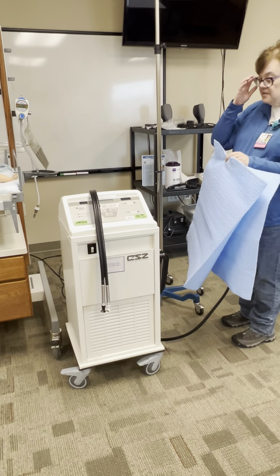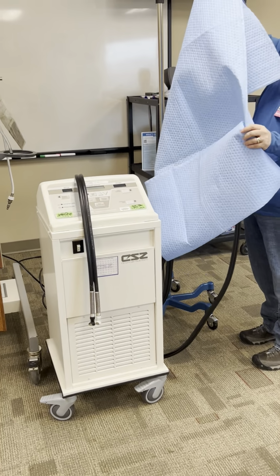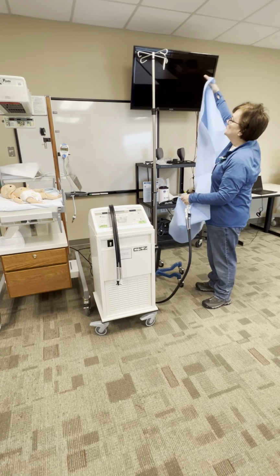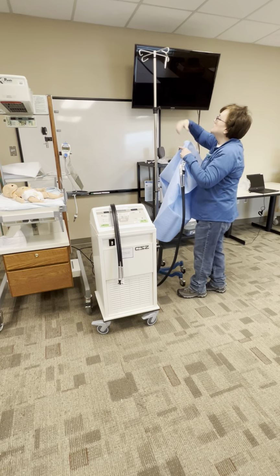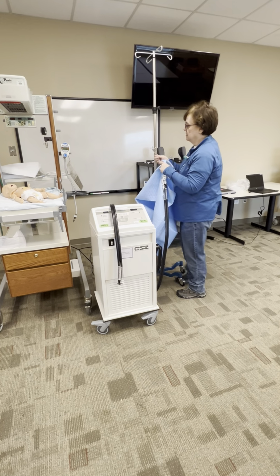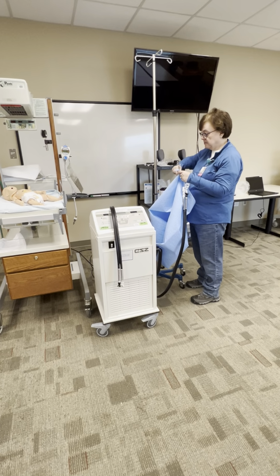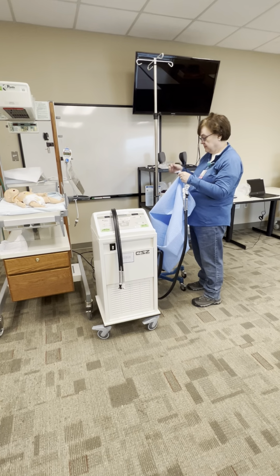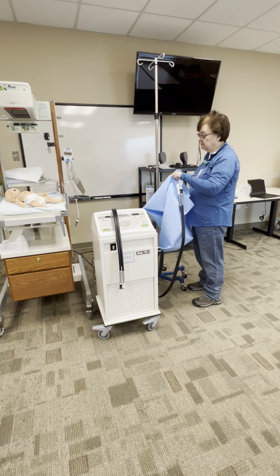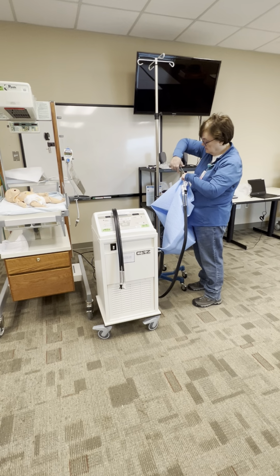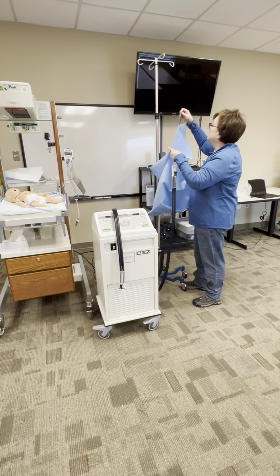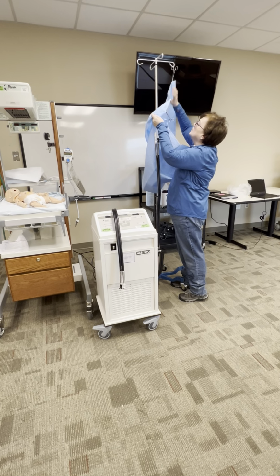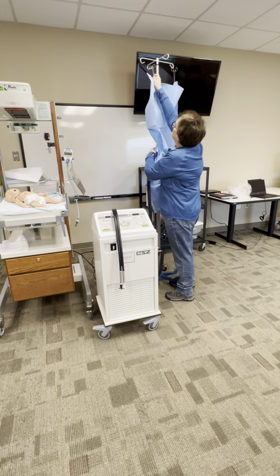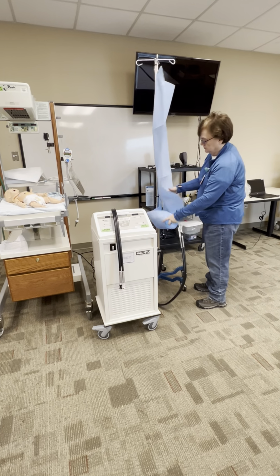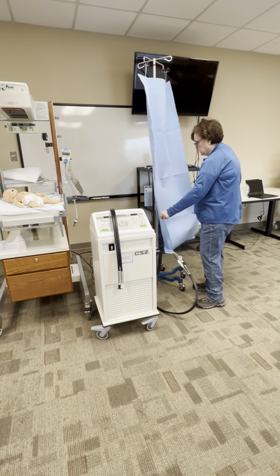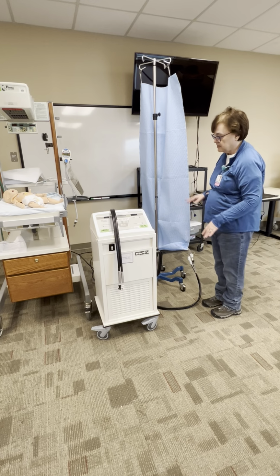This cannot be folded on itself. It can't be laying on anything. It has to be totally open to the air here. I move the IV pole up so it's not going to touch the floor, and I'll take my hemostats and I'm going to connect those on the two ends on the top. Like I said, they don't have to be sterile, but they do have to be clean. And then I'm going to hang those at the top of the pole here. So there you go. It's not touching the floor. It's not touching anything that's going to make it warm.